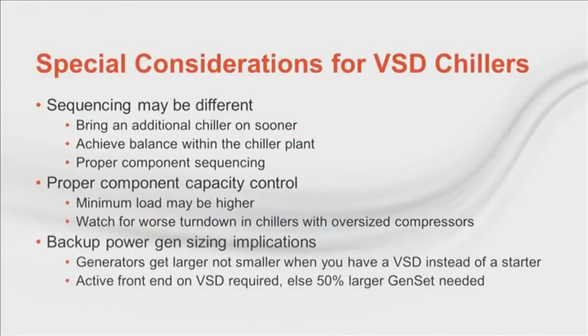You may or may not see this effect in the part load metric IPLV. Work with the manufacturer to make sure that the chiller unloads as you expect it to, both with and without condenser relief, with minimal use of energy-consuming hot gas bypass. And the final consideration we need to check is whether or not we're going to use backup power generation for the chillers. As one of our past newsletters identified, variable speed drives produce nonlinear electric loads and may require larger power generation equipment, not necessarily smaller. Consider this if you are using backup generators with variable speed chillers.